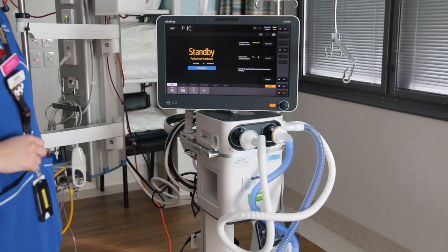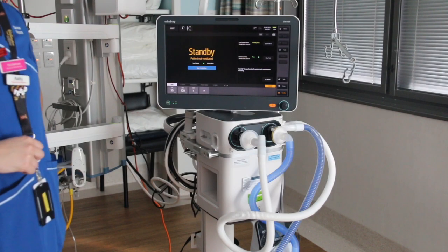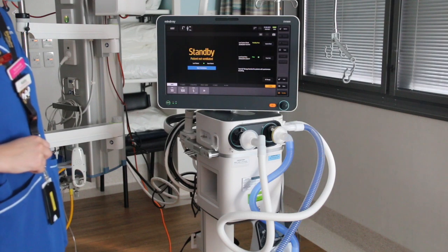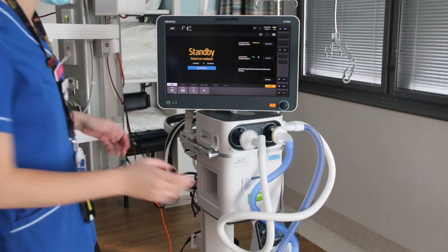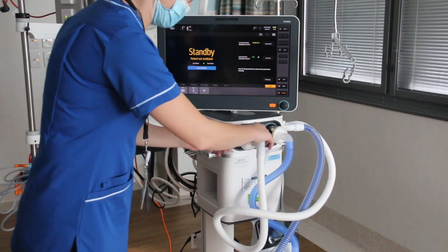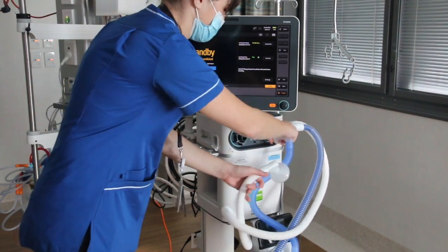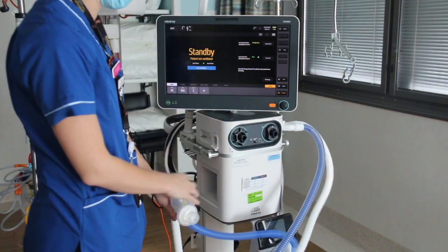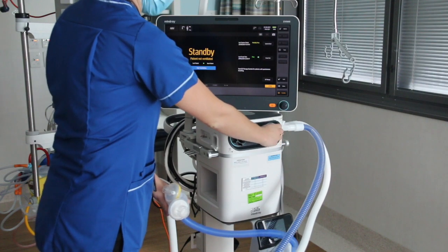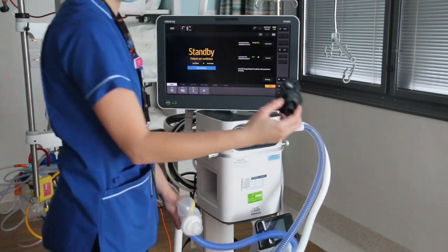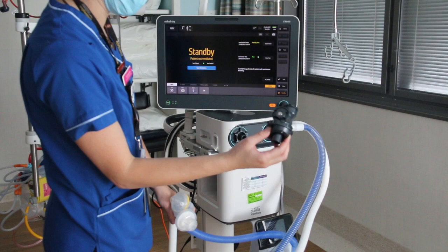This is the ventilator setup for the Mindray SV800 ventilator with a humidified circuit using the Fisher & Paykel 950. You can see here that we've got the circuit attached. The first thing that you need to do when you're setting up this ventilator is put in the valves. We leave an inspiratory valve in ours all the time. So the valve on the right hand side is your inspiratory valve.